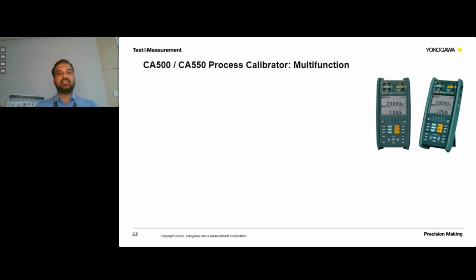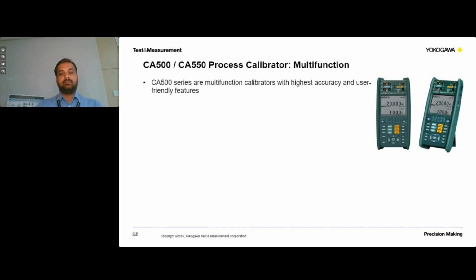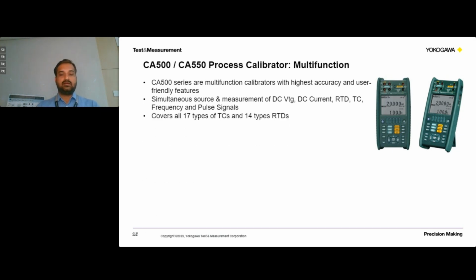Then we have got multifunction calibrator models called CA500 and CA550. These calibrators will cover your basic process requirements, such as process source and measurement parameters such as voltage, milliamps, thermocouples, RTD, frequency, and pulse. It has also got loop power capability, and built-in sweep functions to create various source patterns as per application requirement. It covers all 17 types of thermocouples and 14 types of RTDs with the accuracy of 0.015% of the setting for the source section, and 0.015% of the reading for the measurement section.